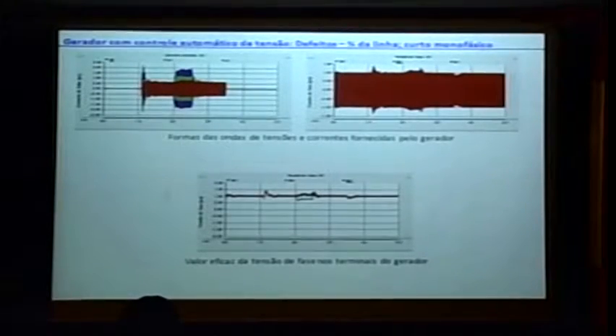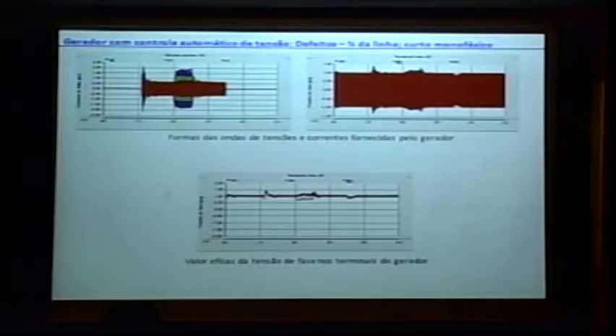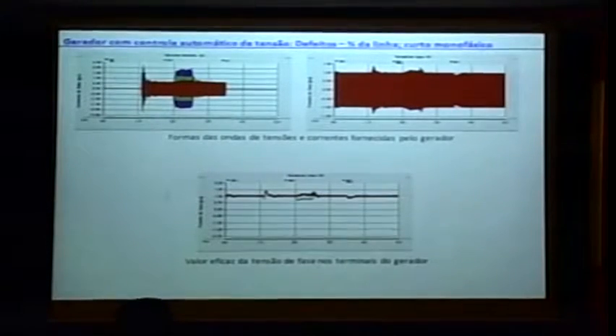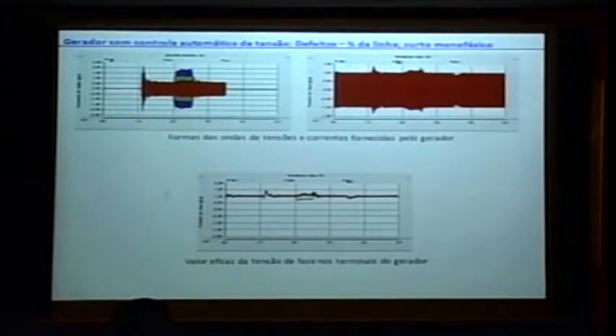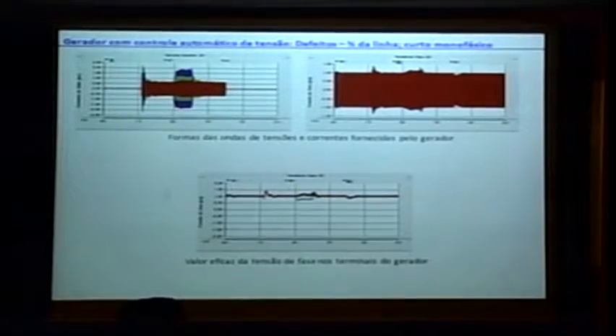This here shows the currents. So, in the shorted phase, the blue phase here, you're going to have overcurrent, current around 2 pu, and differently from the three-phase case, it is sustained. The current is sustained, which means the protection has to operate quickly in the case of fault.